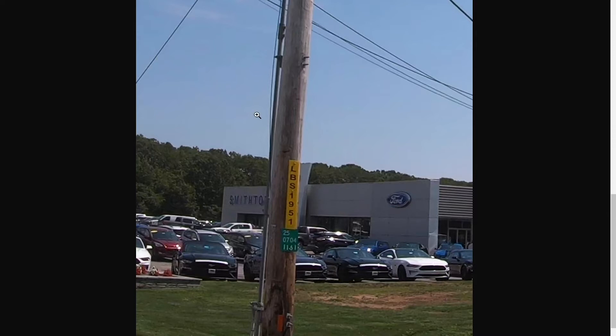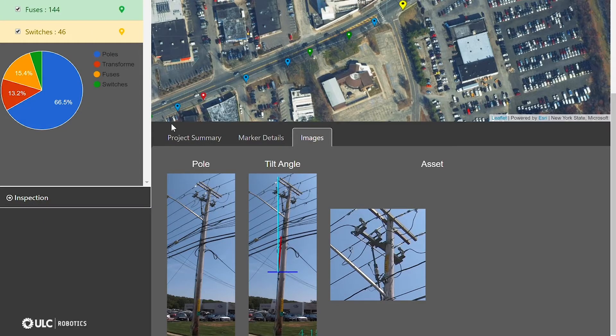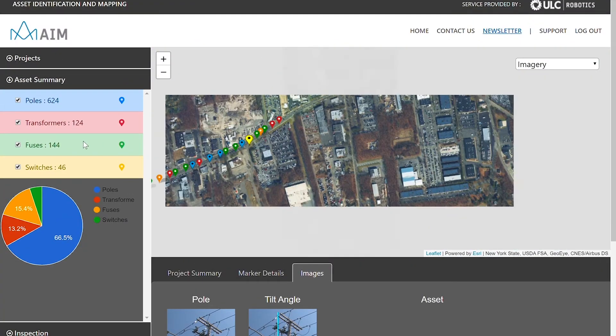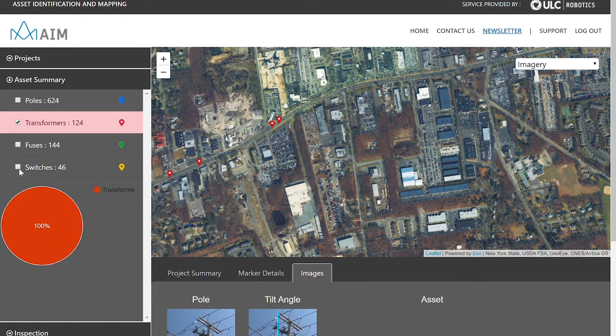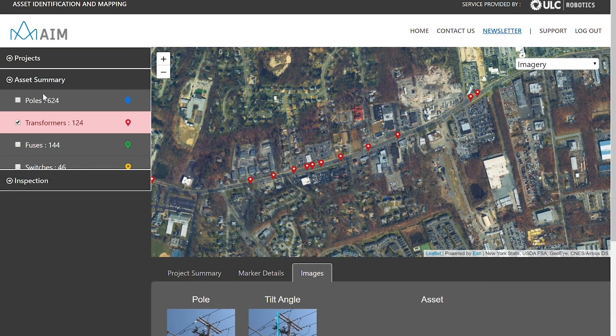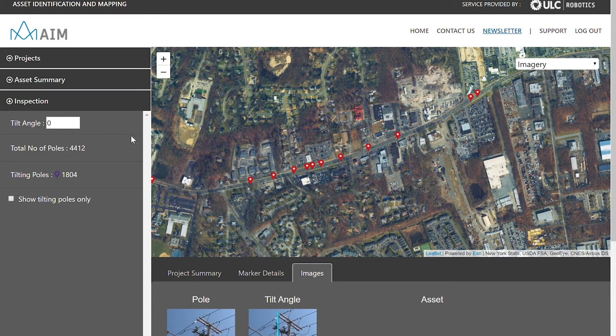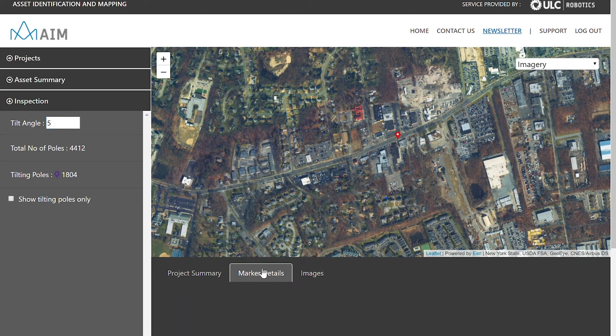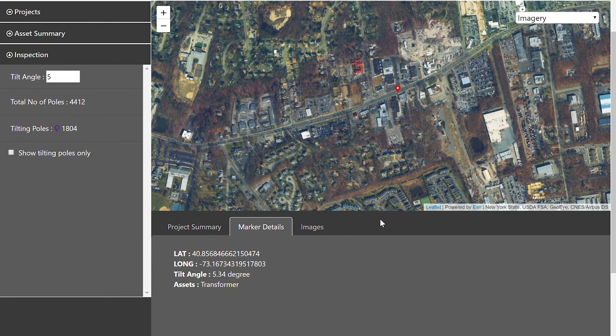The user interface system has an asset summary that allows us to filter out assets within our distribution network. For inspection purposes, I can narrow my data down to just transformers, for example. Taking this a step further, our model is trained to allow us to identify the leaning angle of the pole. If we were looking for a quick overview of problem poles that have transformers on them in a given area, I can increase the tilt angle to whatever is deemed necessary by the utility. This really helps narrow down which poles I need to inspect urgently.